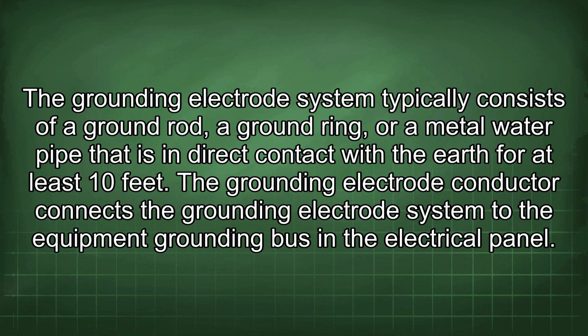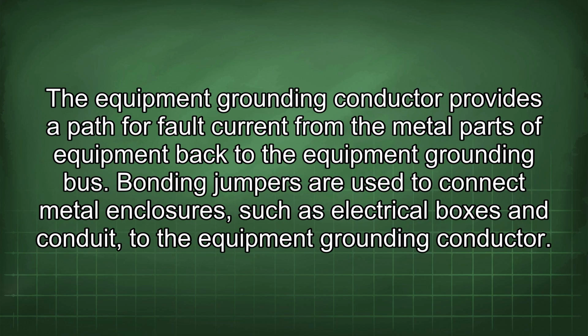The grounding electrode conductor connects the grounding electrode system to the equipment grounding bus in the electrical panel. The equipment grounding conductor provides a path for fault current from the metal parts of equipment back to the equipment grounding bus. Bonding jumpers are used to connect metal enclosures such as electrical boxes and conduit to the equipment grounding conductor.